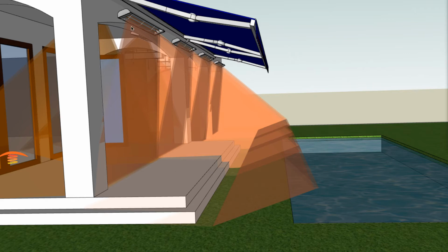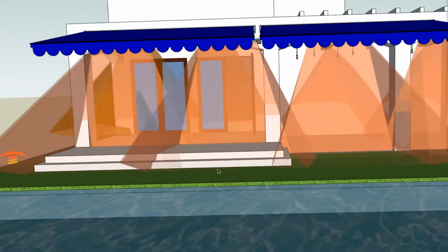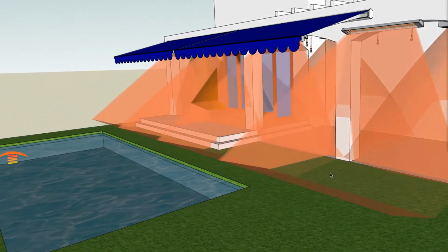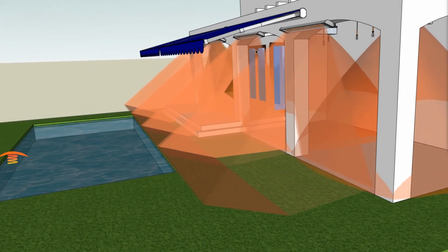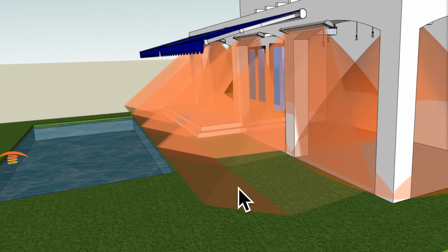You can't accommodate both spaces at different elevations evenly, because the fact of the matter is that for every foot you are away from the surface, the intensities are divided by four on these heaters. And so if you had it at full, this would be hot, and this would be a cooler or just right temperature. You'll never have the same temperatures. But over here, where the step isn't there, these would be a nice heater for this space here.